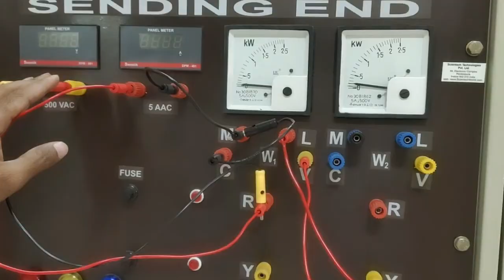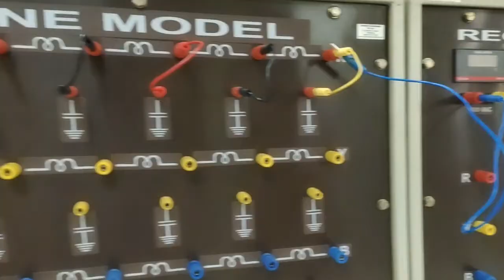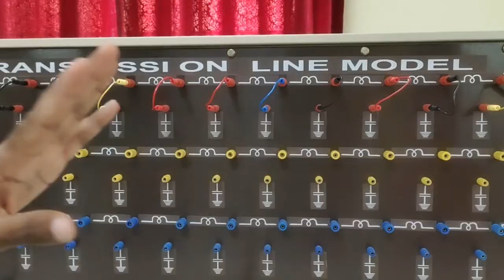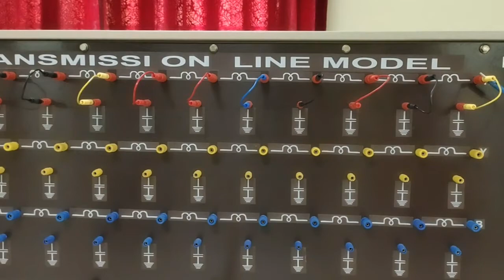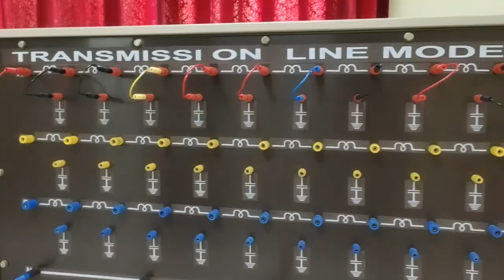As already discussed in the manual, we are giving the supply at the sending end, and the receiving end side can be connected as open end or short end. We calculate ZSO and ZSS: ZSO means sending end supply with the receiving end open circuit, and ZSS means sending end supply with the receiving end short circuit. We take voltmeter, ammeter and wattmeter readings. Now I am discussing only the case where the sending end has the supply and the receiving end is open or short.